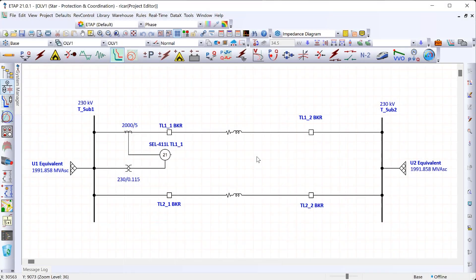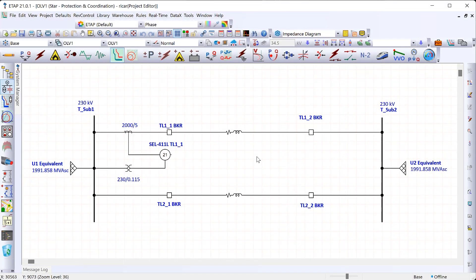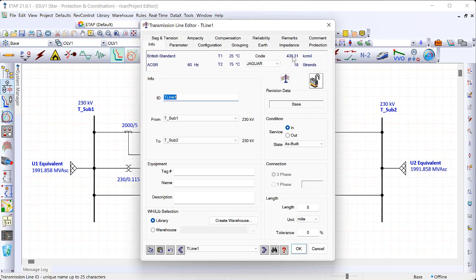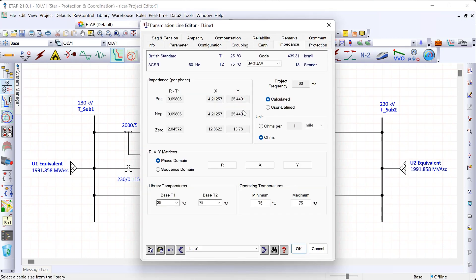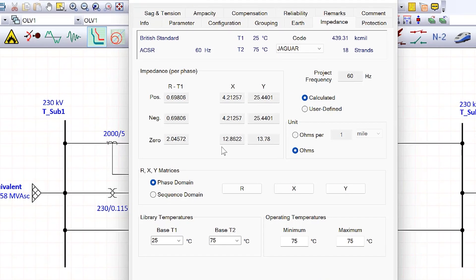Let's jump back into the model and see how we can calculate both the reaches of the zone one and zone two elements as well as the zero sequence compensation factor. If we open the transmission line and go to impedance, we can see that the zero sequence impedance is larger than the positive sequence impedance, though that changes based on the construction of the transmission line itself.